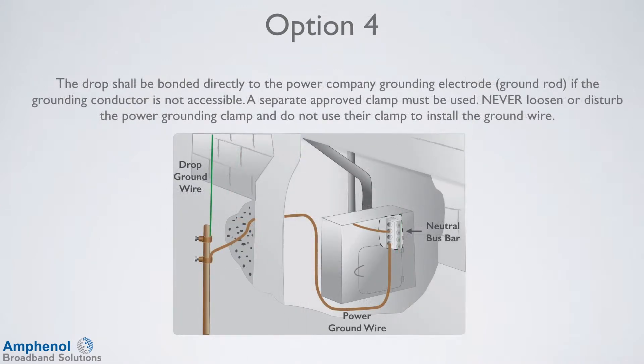In option number 4, if the grounding conductor or ground wire is not accessible, the drop can be bonded directly to the power company grounding electrode or ground rod. A separate approved clamp must be used. Never loosen or disturb the power grounding clamp, and do not use their clamp to install the ground wire to make room for yours.